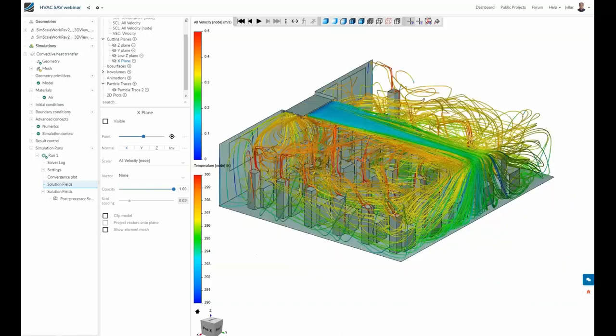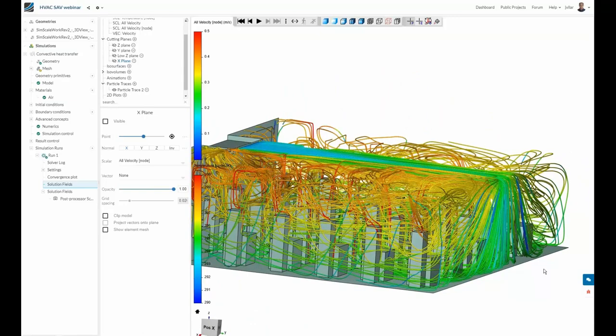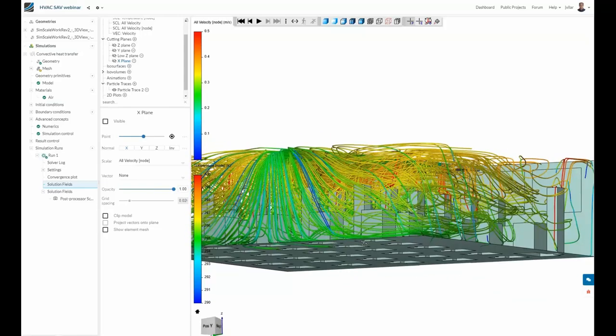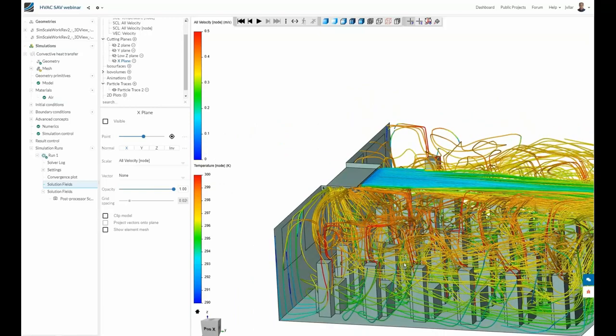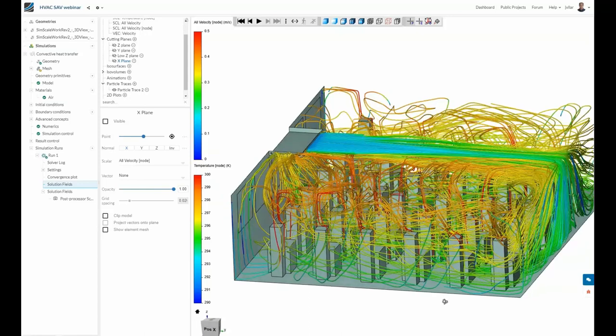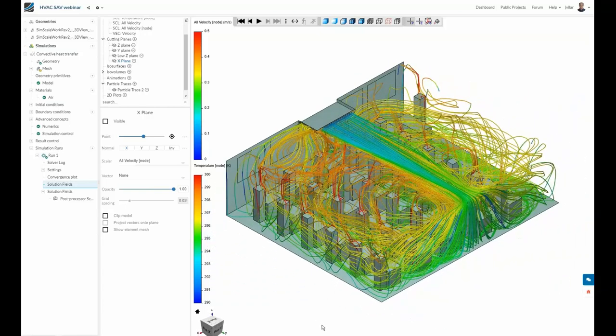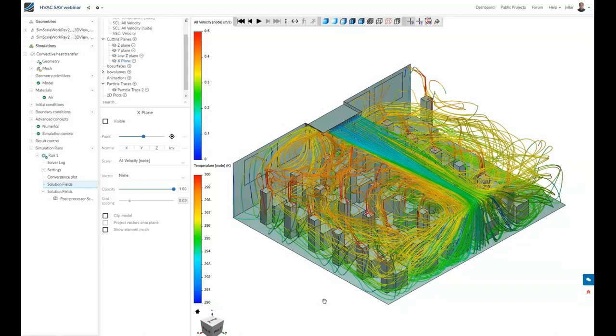With these particle traces, I know it's a bit crowded. But you can really see this Coanda effect, how the air is coming really laminar at the ceiling, and how it creates this Coanda effect you were talking about here, and how it distributes all over the room. Yeah, it looks brilliant. I think you were sort of leading me towards, well, what the next step for us is from what you see now is to actually spread that air distribution outwards a bit. What we didn't take into account when we simplified our initial models was that there are lamella on the supply grill into the room. So, we can actually angle the airflow to spread out across the room a bit more. In this case, it's very direct. It's a jet, basically. The reality is it spreads out more than that to the sides. And that would give you a better, more even air distribution across the room. Exactly.